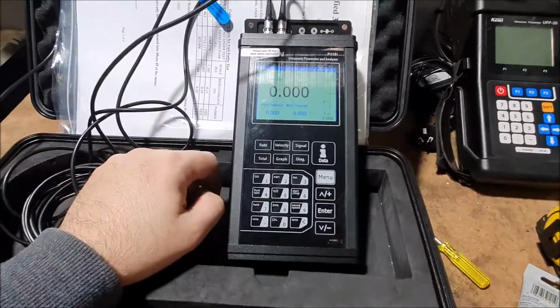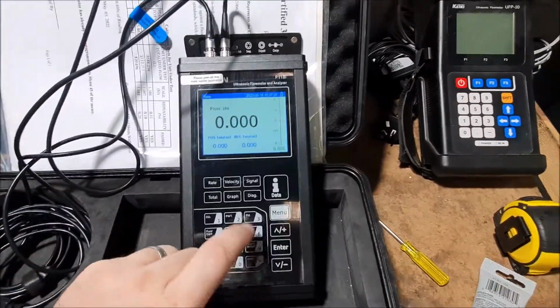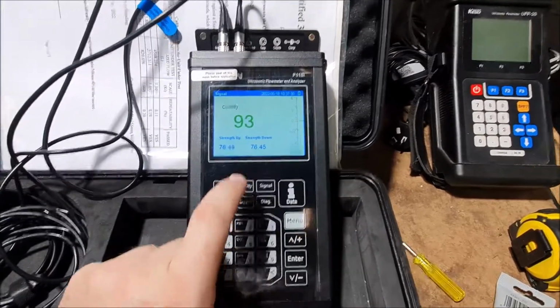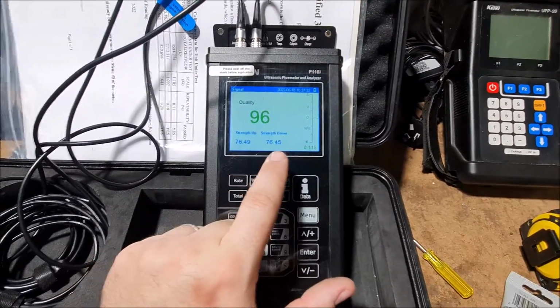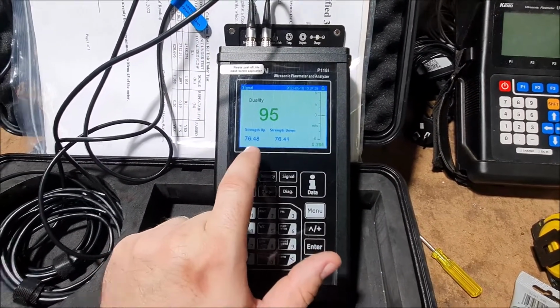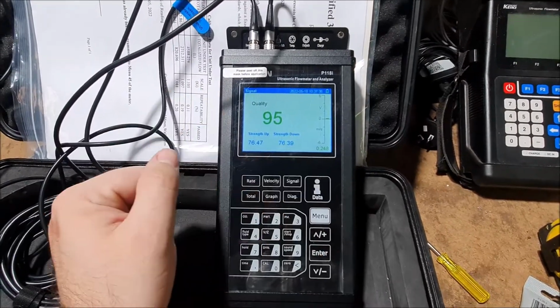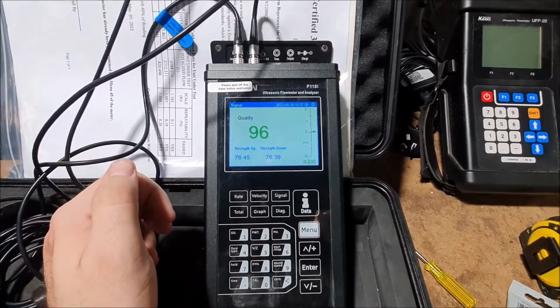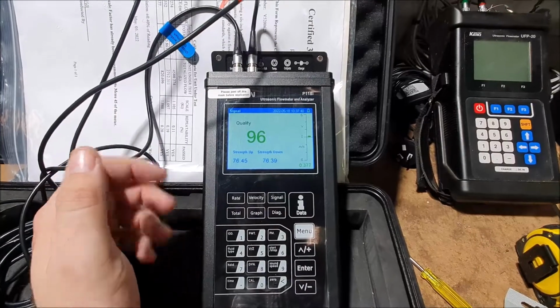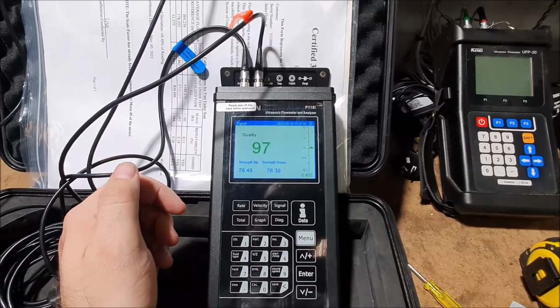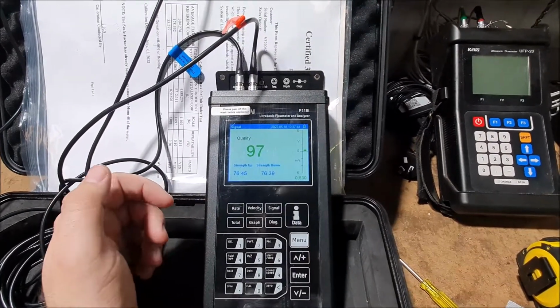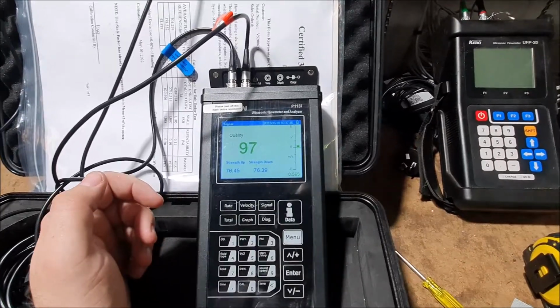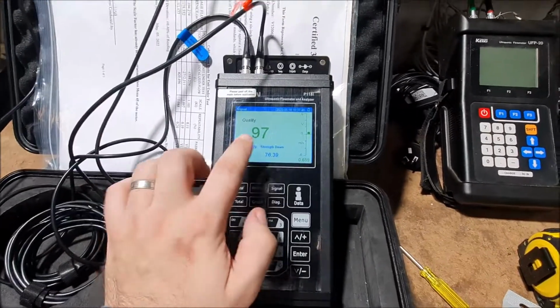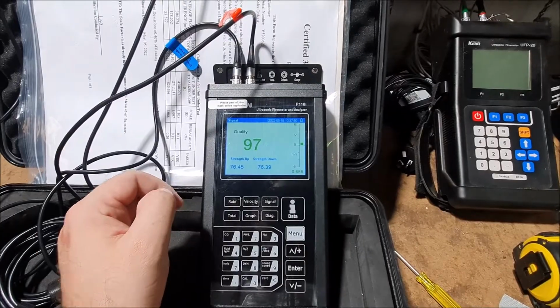okay, we need to check a couple values of importance. One of them being the signal. These values are just signal values of the transducers. All of these you basically want to have over a value of 60. Higher is better, and perhaps if your signal is low, you might need more couplant, or maybe your transducers are incorrectly mounted, or something like that. In this case, it's good. At 97, that's over 60.